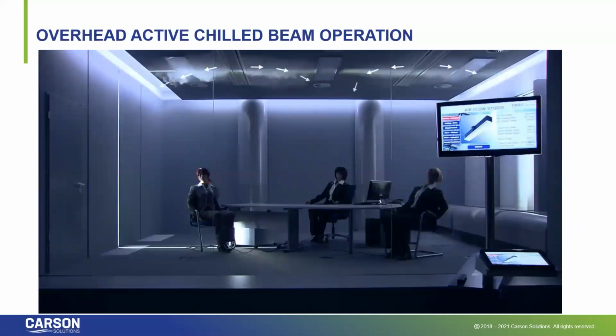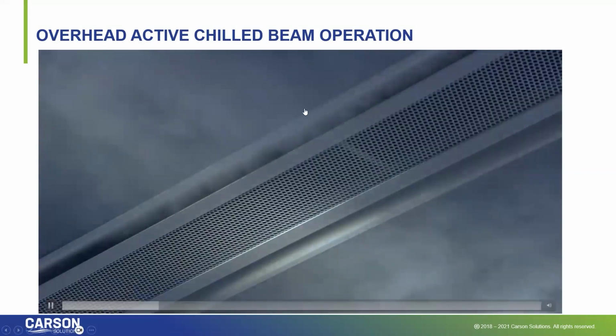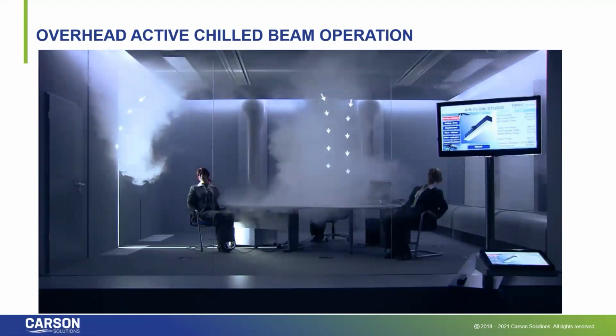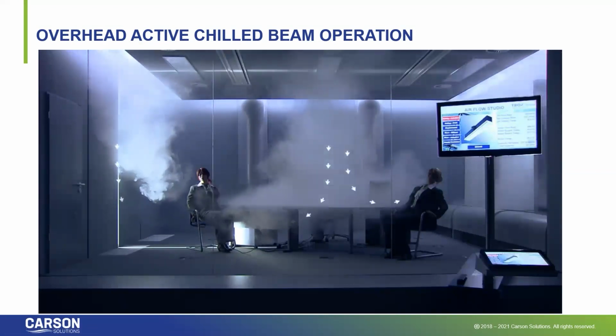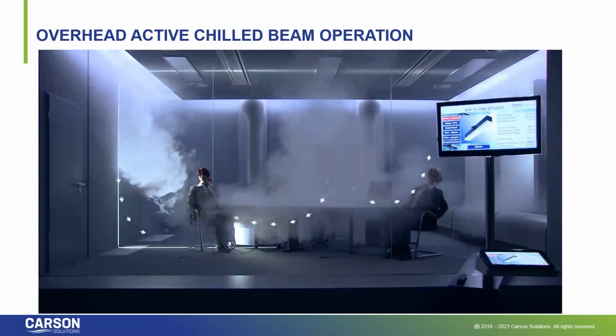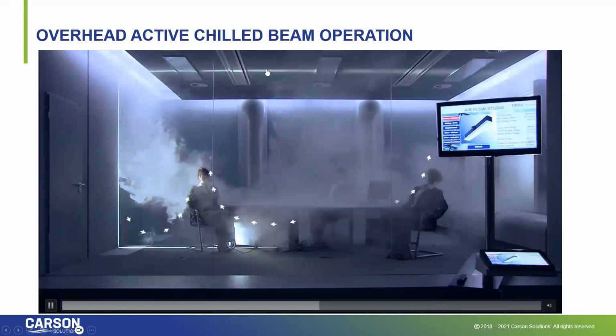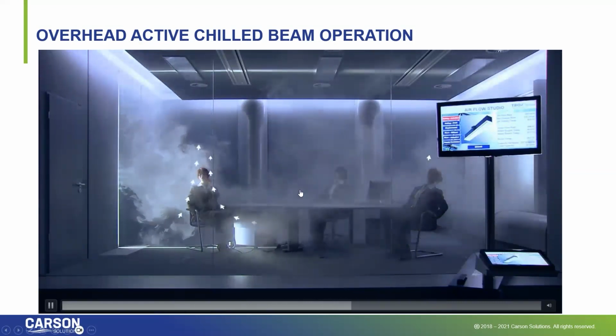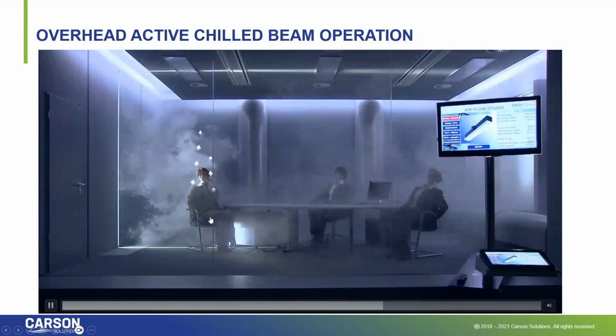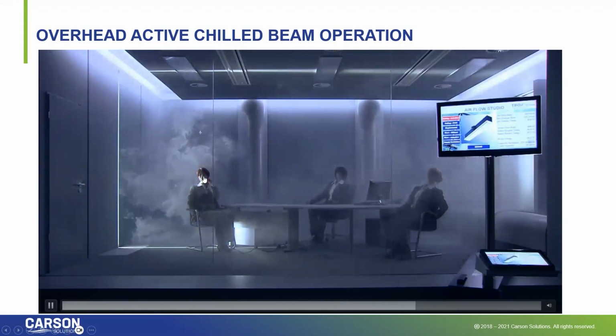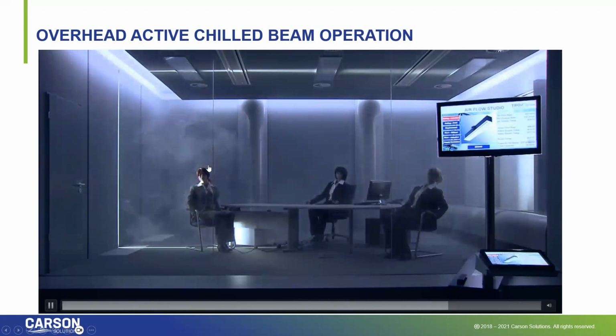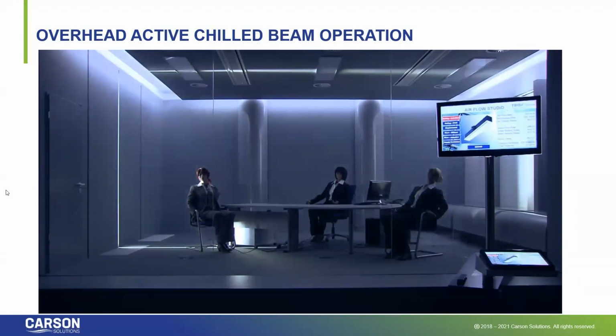So here's a video of typical operation of an overhead chill beam. Watch the air as it comes out of the diffuser. It clings to the ceiling via the Coanda effect until it comes in contact with a wall or an adjacent airstream, and pushes that air slowly into the space until it comes in contact with a heat source, which then delivers that warm, buoyant air back up to the chill beam to repeat the process.